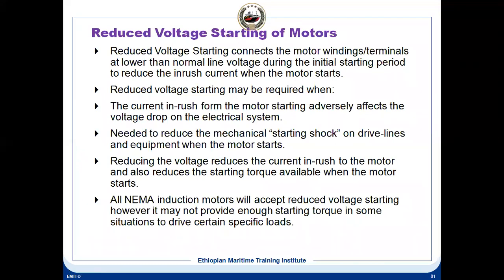Reduced voltage starting connects the motor winding terminals at a lower voltage than the normal voltage during the initial starting period to reduce the inrush current when the motor starts. The current inrush from the motor starting adversely affects the voltage drop on the electrical system. So that is also another factor. You cannot start a motor with a very high starting current, as it can affect the whole system on board ship. That is the reason we use reduced voltage starting.